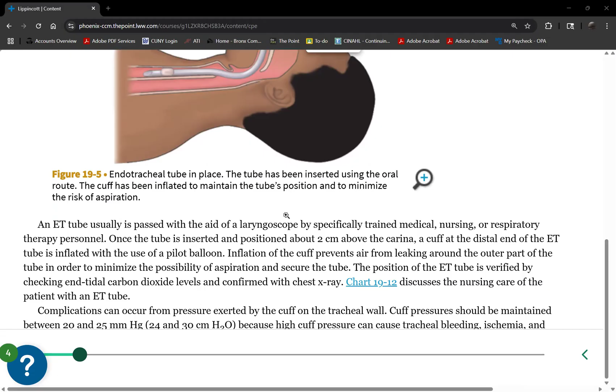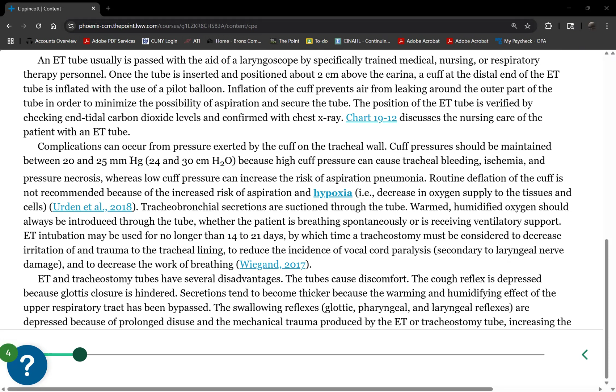That's another question. Here's your pressure. Cuff inflation pressure must be between 20 and 25 millimeters of mercury, 24 and 30 centimeters of water. Now, how do we measure that pressure? Not shown here, but you probably noticed on our mannequins the small little tube coming out with a little balloon at the tip. We call that the pilot balloon. The pilot balloon is where you attach a syringe filled with air, and then we inflate the cuff.